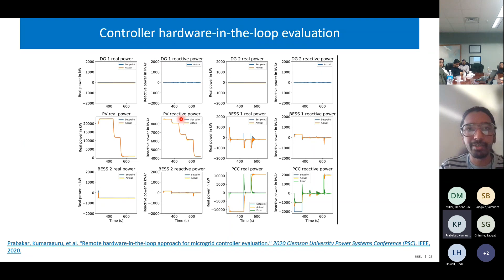This is another project with the same microgrid, but using controller hardware and power hardware. We have this 26 megawatt PV and a battery energy storage system, which we took and modeled as actual power hardware. We had the same PV inverter in the lab with the same firmware that it's supposed to run in the field, and also a similar battery energy storage system that we could find at that time, and then ran power hardware in the loop.